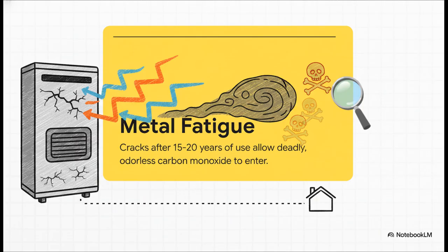Shifting gears to the winter months, we really need to talk about heat exchanger metal fatigue. And I want to be very serious here. This is a structural failure that typically occurs after 15 to 20 years of hard winter usage. The constant daily expansion and contraction from heating and cooling creates microscopic cracks in the metal of the heat exchanger.